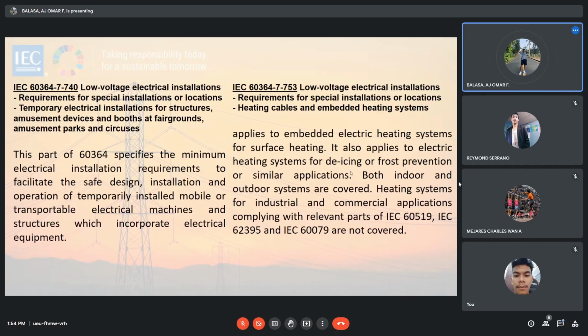Next, IEC 60364-7-753. Heating cables and embedded heating systems. This includes heating systems for walls, ceilings, floors, roofs, drain pipes, gutters, pipes, stairs, roadways, and non-hardened and compact areas, for example football fields and lawns. For wall heating systems, this standard contains additional requirements, for example a metal sheet enclosure grid to protect against the effect of overheating caused by short circuit between live conductors due to penetration of the embedded heating unit. For heating units delivered from the manufacturer without exposed conductive parts, this standard requires a metallic mesh covering.